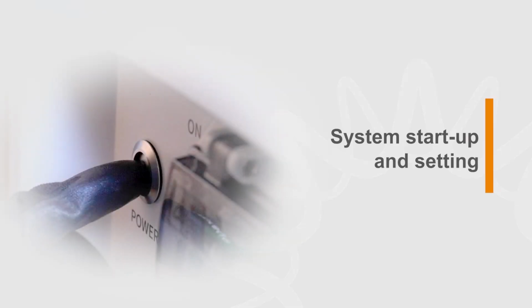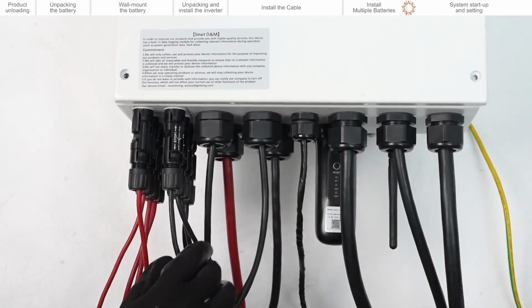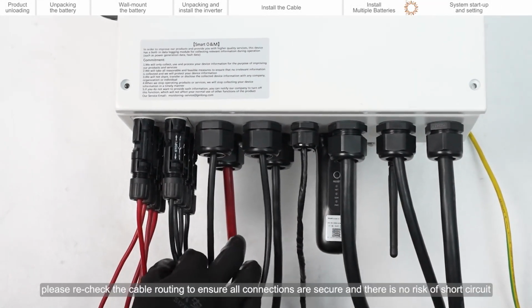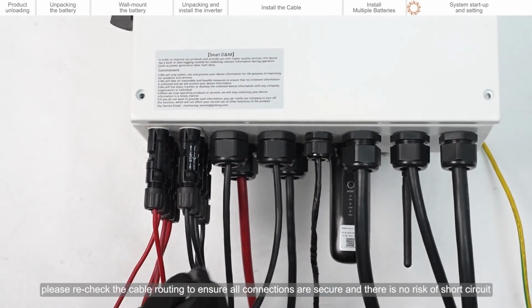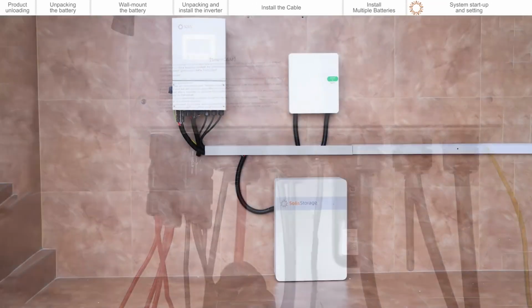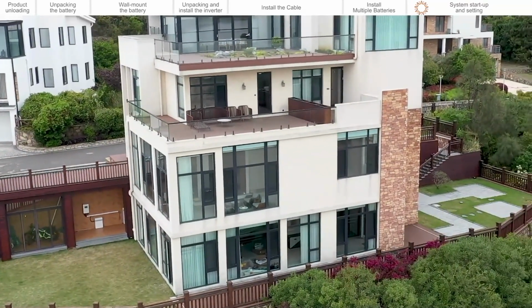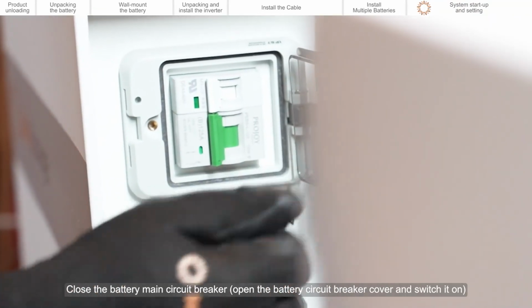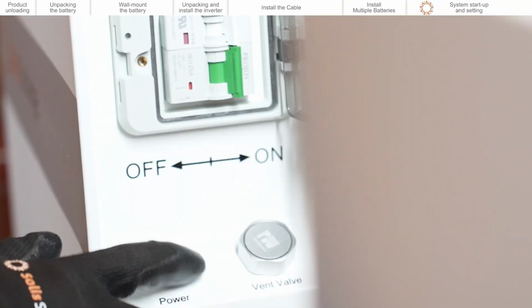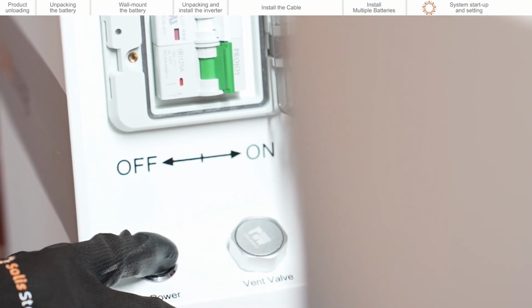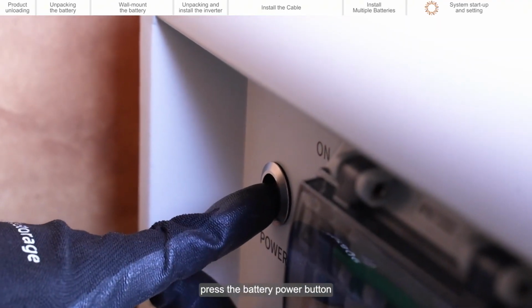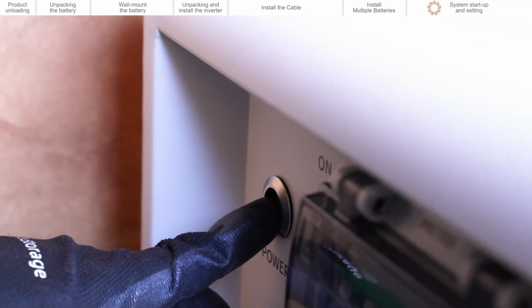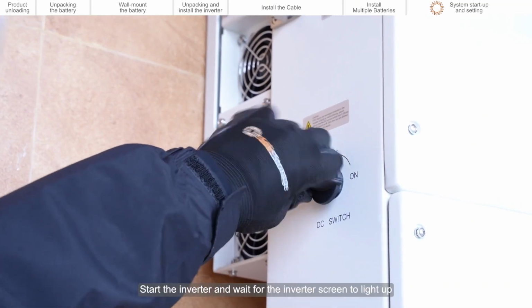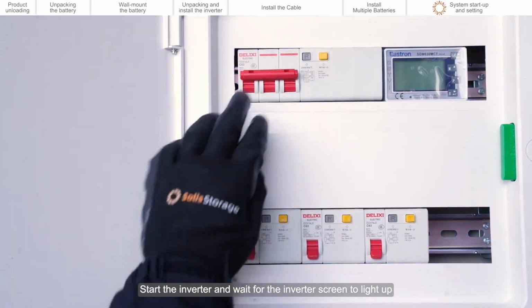System startup and setting. Before starting the system, please recheck the cable routing to ensure all connections are secure and there is no risk of short circuit. Close the battery main circuit breaker. Press the battery power button. Start the inverter and wait for the inverter screen to light up.